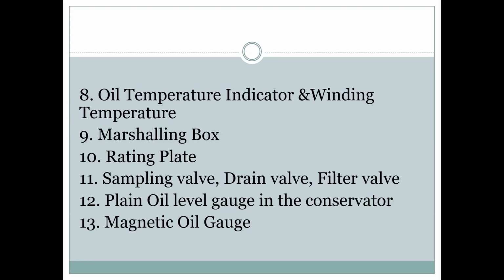So somehow everybody is focusing on the winding not being disturbed. Anything can go wrong, anything can happen with transformer leakage, anything we can take care of at the site. But failure of the transformer is all protected by this, so that the heart does not fail. So the transformer winding is protected. That's why all these accessories have been placed, so that they can protect you.